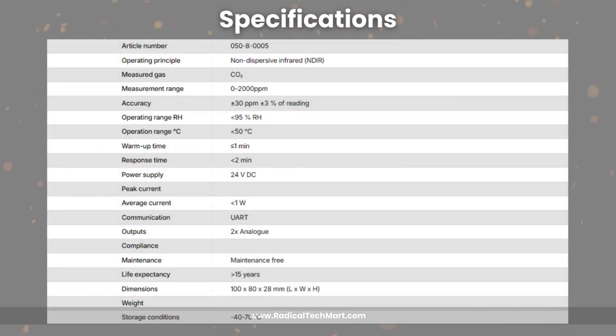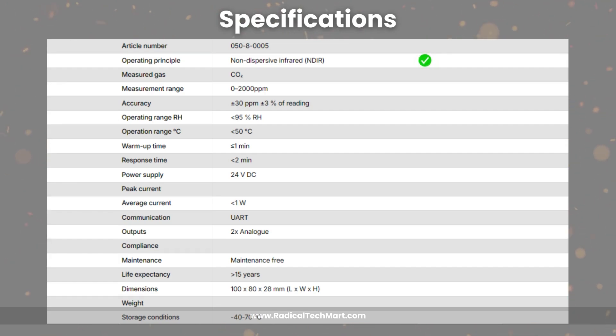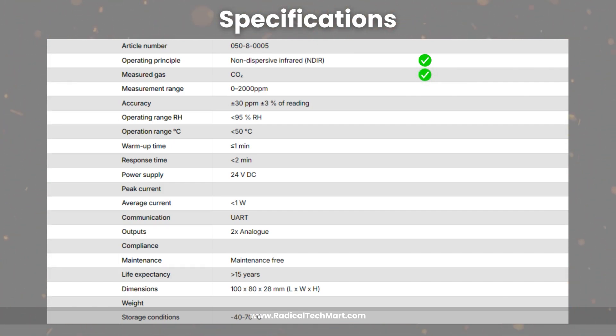Now let's see the specifications offered in the CO2 Transmitter. All standard specifications for the eSense CO2 Transmitter can be seen on screen right now. It is offered with a Non-Dispersive Infrared (NDIR) CO2 sensor, which is the most commonly used sensor type in industries for accurate measurement of CO2 gas. The measuring range offered in this particular transmitter is 0 to 2000 ppm.